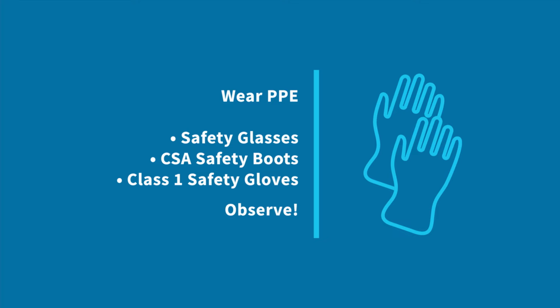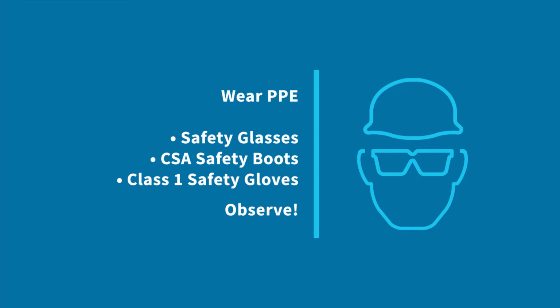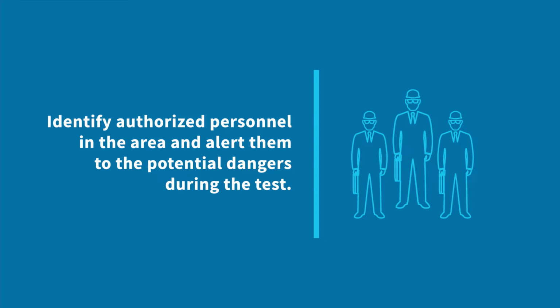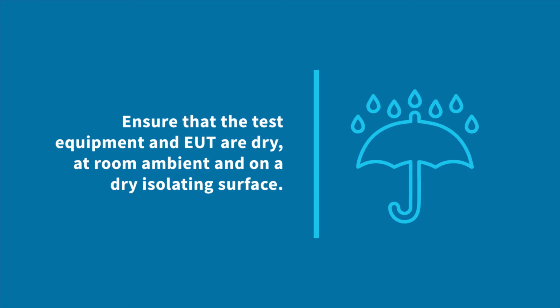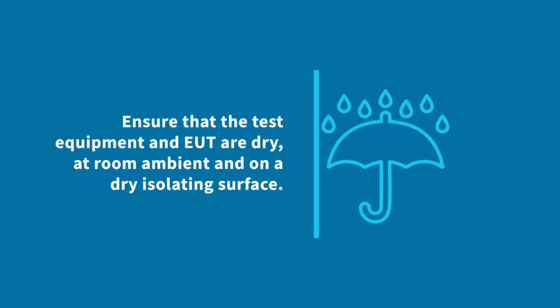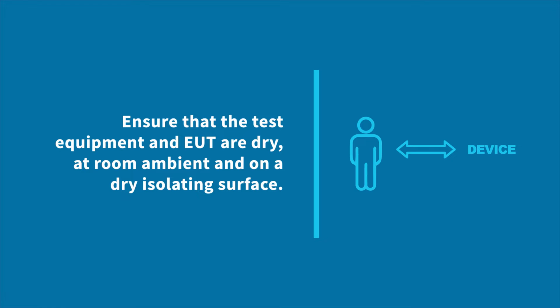Observe other safety measures based on the facility where the tests are to be conducted. Identify authorized personnel in the area and alert them to the potential dangers during the test. Only trained and authorized personnel should be permitted in the test areas. Ensure that the test equipment and EUT are dry at room ambient and on a dry isolating surface. If the use of an isolating surface is not possible, ensure no part of the surface, for example a metal cart, is energized during the test.